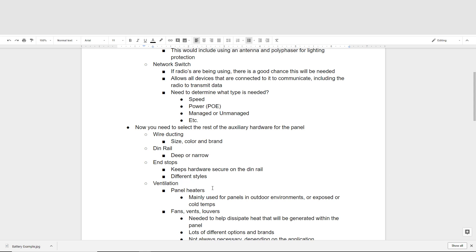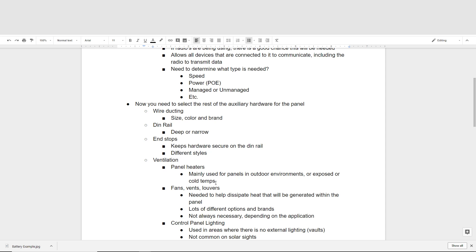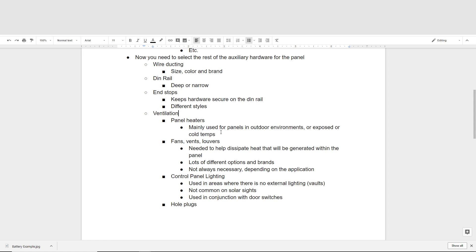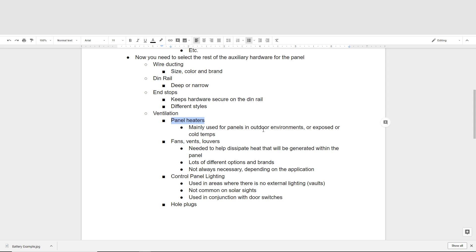The next thing we want to look at is our ventilation needs. There are a lot of different options here, and you want to make sure you take your time and get it right. You can do heat calculations to make sure your panel is not getting too hot or cold, then size the ventilation hardware accordingly. One very common piece of hardware is panel heaters, typically used in areas where you have access to at least 120-volt power. These are mainly used in outdoor environments exposed to extreme cold temperatures where the hardware within the control panel cannot tolerate those conditions.